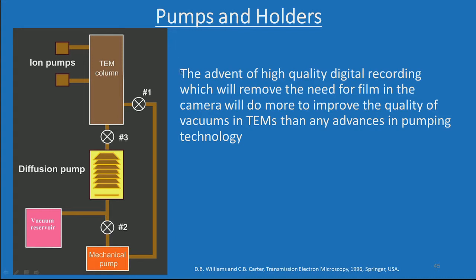There are various pumps — diffusion pumps, ion pumps, and vacuum pumps. I will give actual details during the laboratory demonstration. To give a general comment: the advent of high-quality digital recording, which removes the need for film in the camera, will do more to improve vacuum quality in TEMs than any advance in pumping technology. Today we completely record all information in a digital recording system, though some microscopes still use plate films.